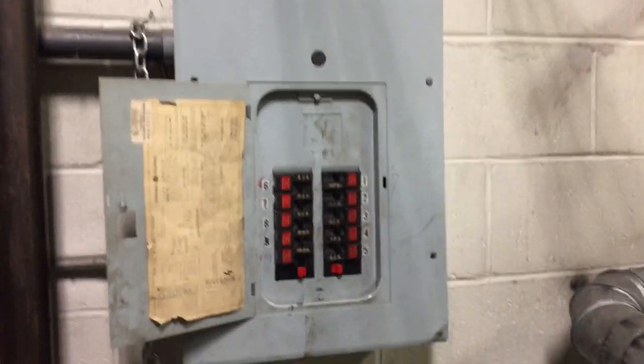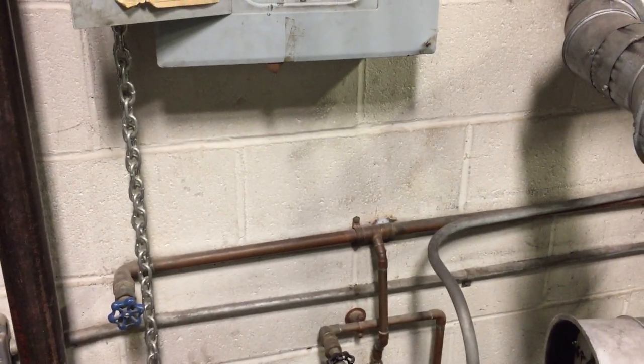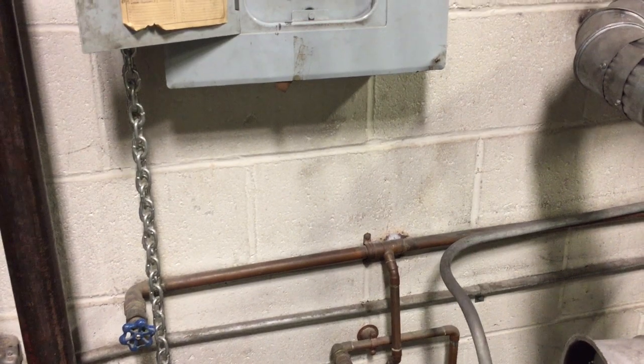In this episode of Moving Violations, we'll be taking a look at the dedicated space directly below this panel board. You see those water lines there — that's a violation.